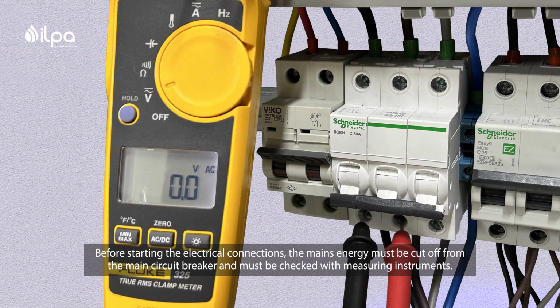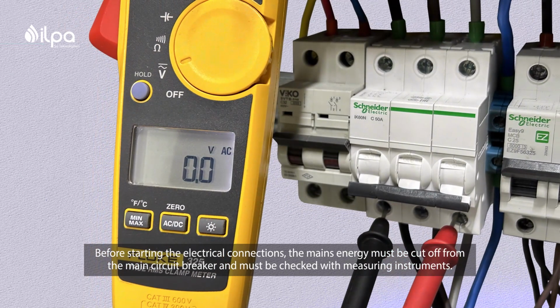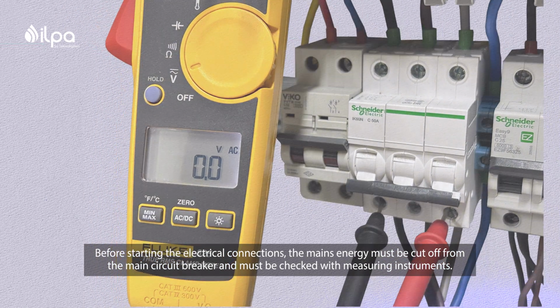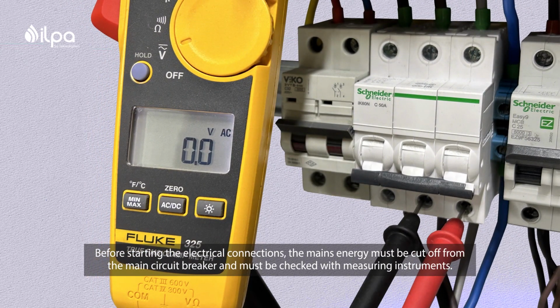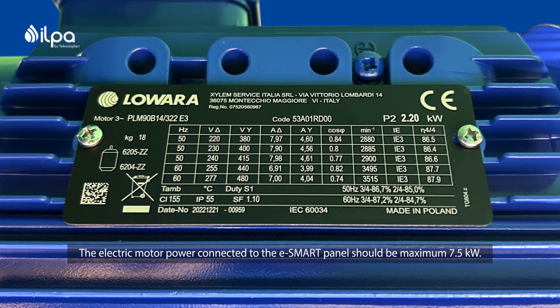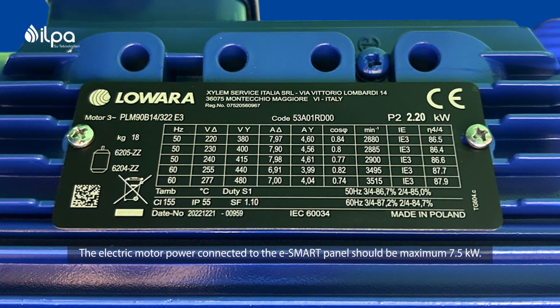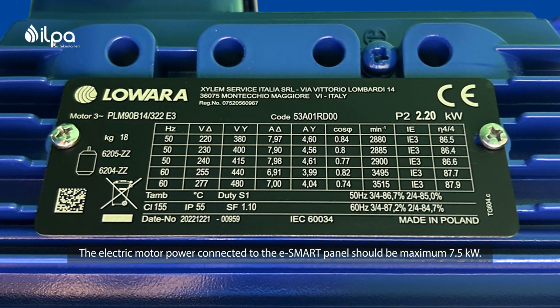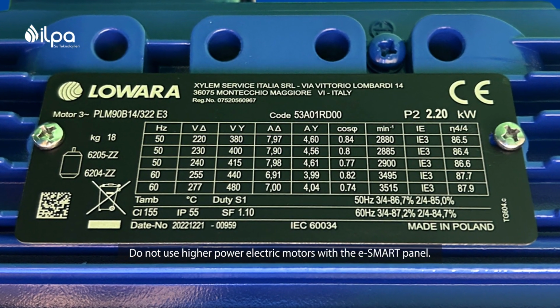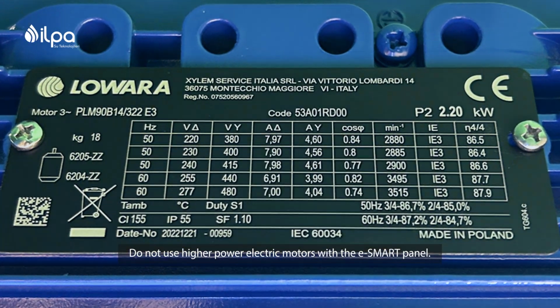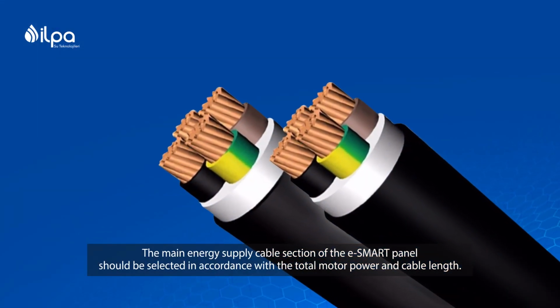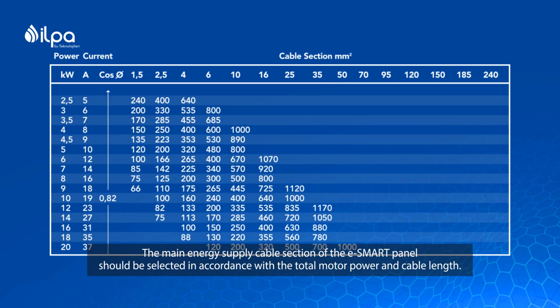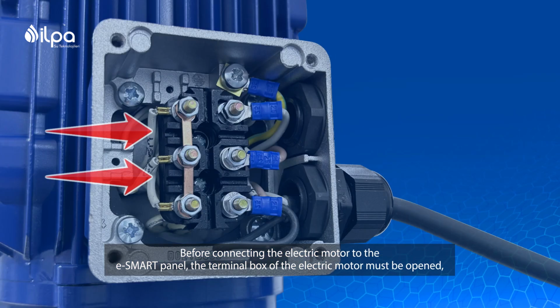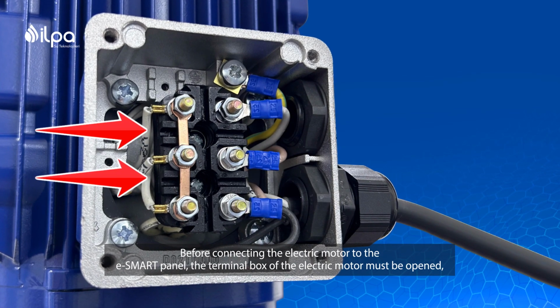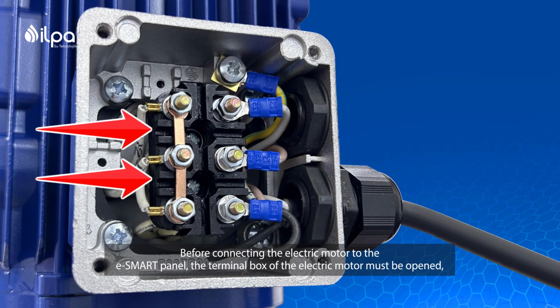Before starting the electrical connections, the mains energy must be cut off from the main circuit breaker and must be checked with measuring instruments. The electric motor power connected to the eSmart panel should be maximum 7.5 kilowatts. Do not use higher power electric motors with the eSmart panel. The main energy supply cable section of the eSmart panel should be selected in accordance with the total motor power and cable length.